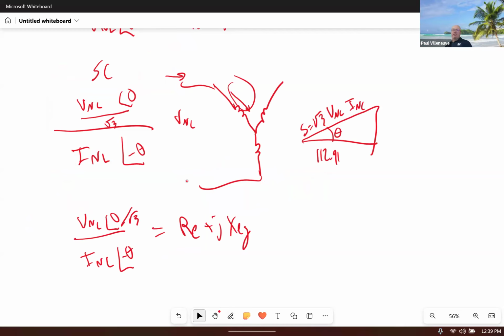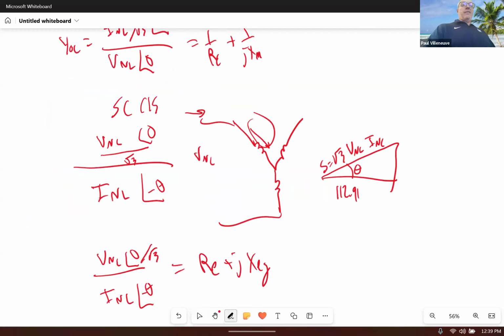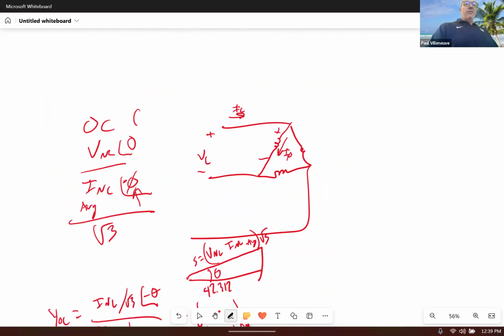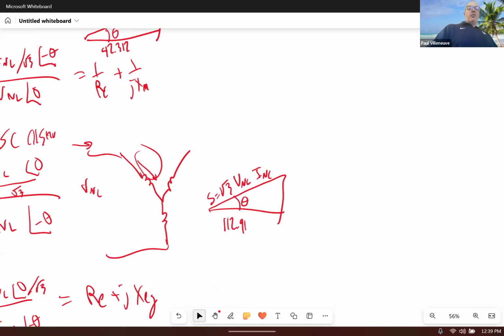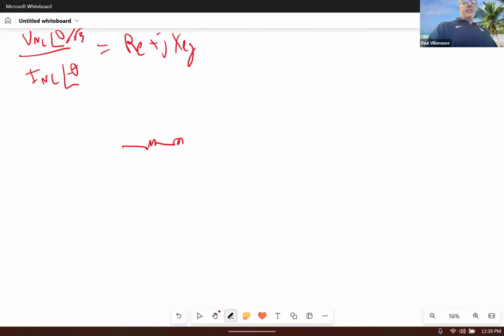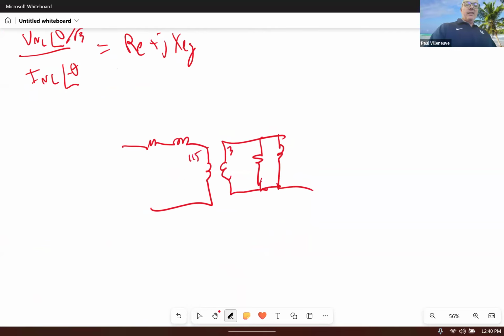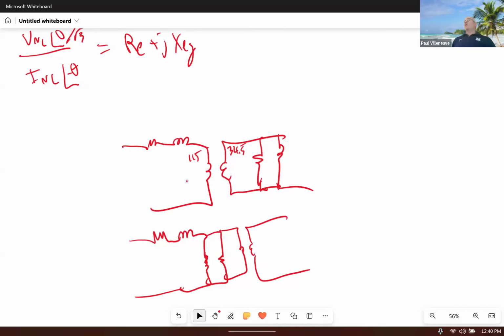There's one last thing you need to do to get the answer. This short circuit test was on the 115 kV side. This one over here was on the 34.5 side. So if you're going to draw your equivalent circuit, you needed to draw it like this. Right? Those impedances are like that. So this is the 115 and this is the 34.5, or you could have drawn it this way, and you can pick whichever winding you want. You can reflect them over to one side or the other of the transformer. You just have to reflect one pair of data points there. So either RC and JXM get reflected to the high side, or RE and JXE get reflected to the low side.